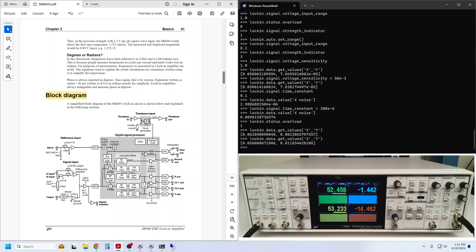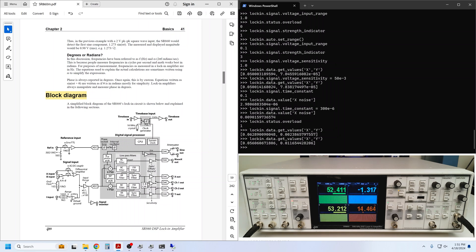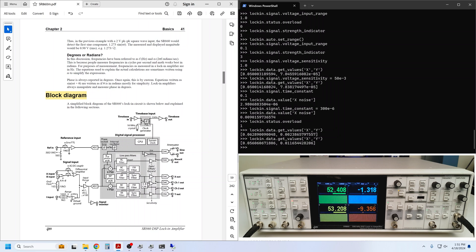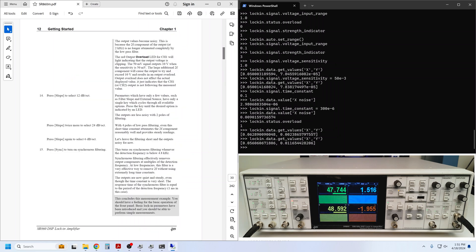If you're wondering why the queried values are not overloaded, it's because in a DSP lock-in, once the input signal is digitized by the ADC, the phase-sensitive detection and subsequent low-pass filtering are all digital operations in the digital signal processor, just operating on a stream of numbers. A query of X, Y, R, and theta simply return those numbers with their full floating point precision. Meanwhile, the output overload is occurring because the lock-in is trying to gain up those measured numbers by the sensitivity factor. This would result in an output voltage larger than what the analog circuitry can provide.